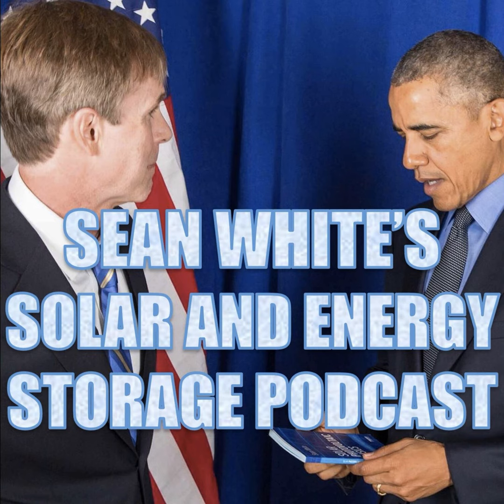So you turn off this disconnect, and both sides of that disconnect are going to be dangerous to touch. One side, while the sun's up, is still dangerous. And the other side, for 5 minutes after it's been turned off. And I shouldn't even say only when the sun's up on the PV side, because even when the sun goes down, you can get voltage from moonlight, or bright lights shining on something. Even people have been hurt by flashes of lightning causing light to energize the PV system and knock people down. So be careful. Especially when you're on a roof, always wear fall protection.